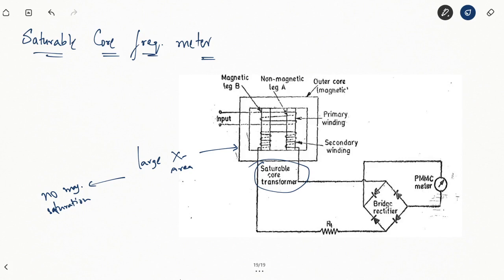Then you have this leg of the transformer, leg A, and this will be a non-magnetic material. And similarly leg B, but this leg B will be a magnetic material. You have windings, the primary winding and the secondary windings, that will be wound around these legs. So the outer core is magnetic material with a large cross-sectional area so it does not saturate easily, leg A is non-magnetic, and leg B is magnetic.